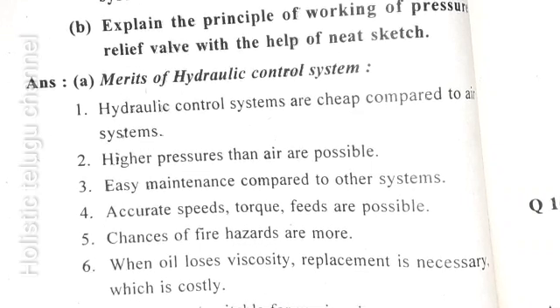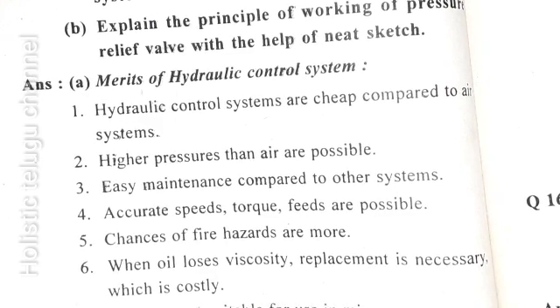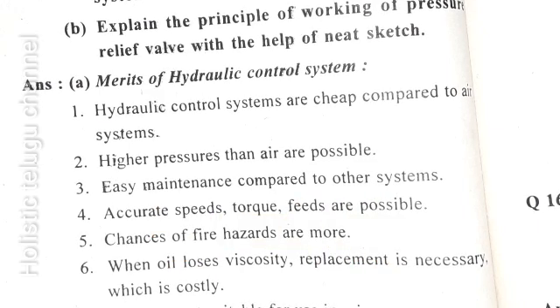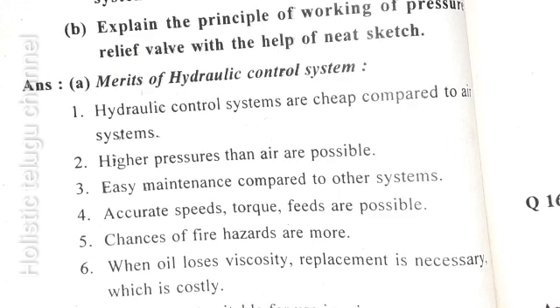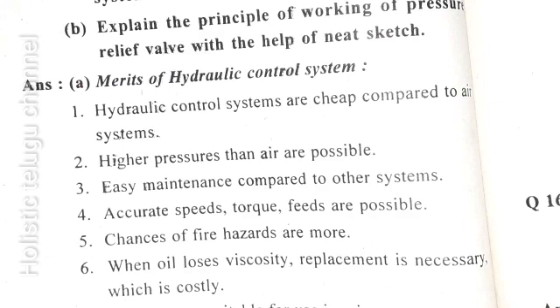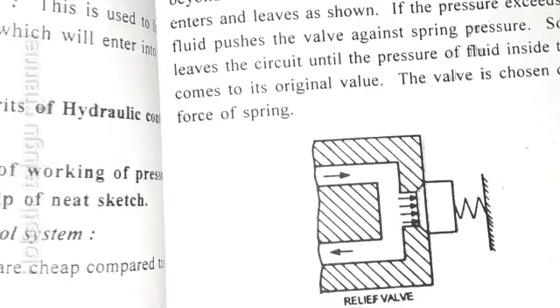Merits of hydraulic control system: comparing to air systems, higher pressures are possible. Easy maintenance compared to other systems. Accurate speed, torque, and feed are possible. Demerits: chances of fire hazards are more. When oil loses viscosity, replacement is necessary which is costly. They are not suitable for use in mines. Leakage will create unwanted effects. Control systems work effectively if the fluid flow is laminar only. Operation becomes slower if the control pipes are lengthy.